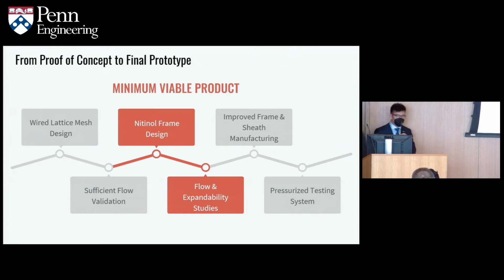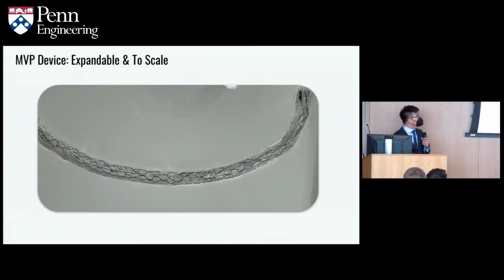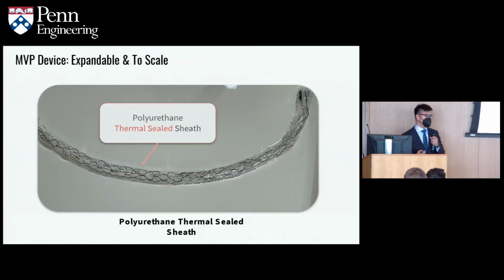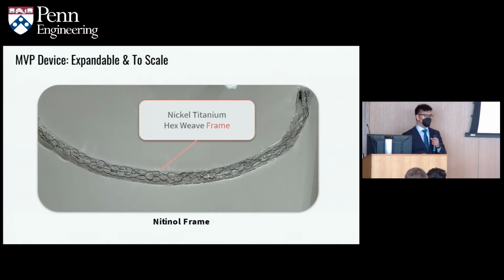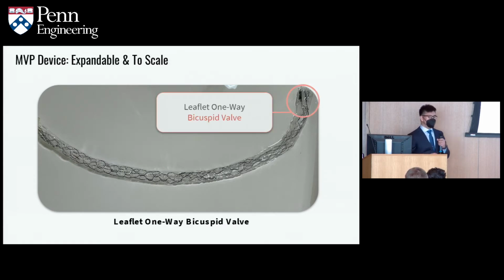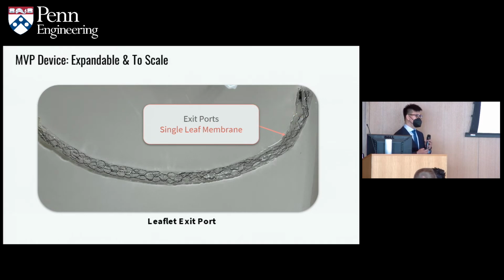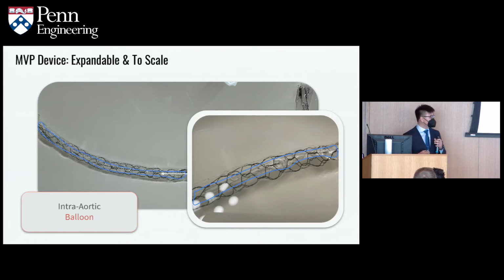Thanks, Will. So for our MVP, we upgraded from the wire mesh by creating a nitinol frame and used this to conduct flow and expandability studies. Our MVP consisted of a polyurethane sheath on the outside that was thermally sealed, followed by a nitinol frame on the inside. At the inlet of the device, we created a leaflet one-way bicuspid valve to allow unidirectional flow into the device. And near the inlet, we also created an exit port with a single leaf membrane to allow unidirectional flow out of the device. And following the sheath and the frame, we inserted the balloon pump, which is outlined here in blue.